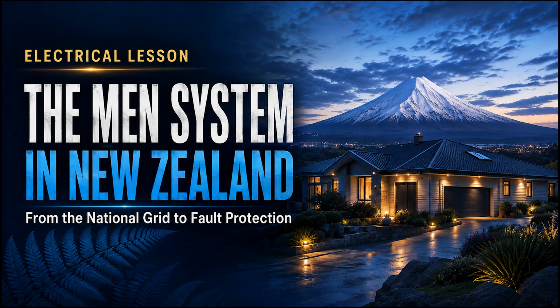In a healthy MEN system, most fault current normally returns through the metallic protective earth, MEN link, and neutral or PEN path. The soil path is parallel and usually has higher impedance. Misunderstanding 3. An earth wire has no voltage, so it can never be dangerous. During a fault, a protective earthing conductor carries current and can develop a voltage because every real conductor has impedance. A broken neutral condition can also raise the complete earthing system above local earth potential.